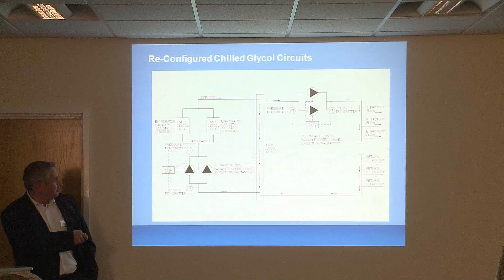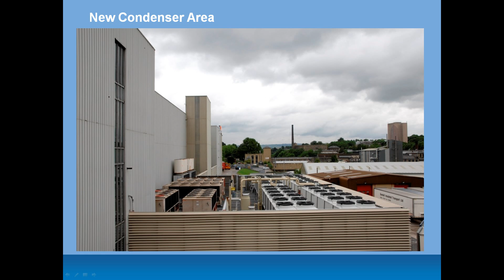So this was the plant which was installed originally - classic chiller plant. It's R22, which was one of the imperatives for swapping it out, but at the same time, it really wasn't terribly good when it was new. It's been looked after not very well, and it's just drifted - all dirty, fixed speed fans - and what we installed was some heat rejection here.